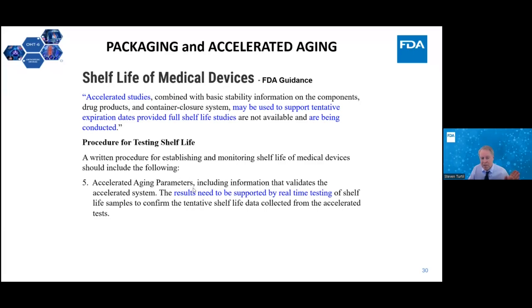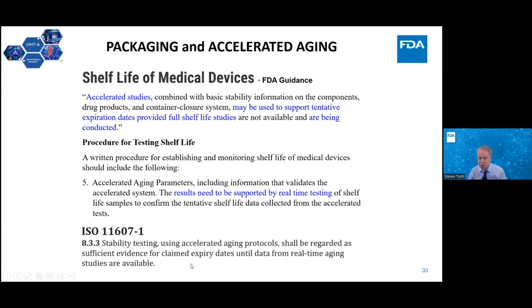And so it's going to give you the calculations, including information that validates the accelerated system. Results need to be supported by real-time testing. That's the second column. And there we go. This is a direct quote from 11607. Stability testing using accelerated aging protocols shall be regarded as sufficient evidence to claim expiry dates until data from real-time aging studies are available.